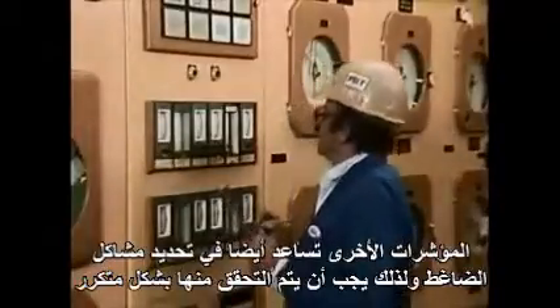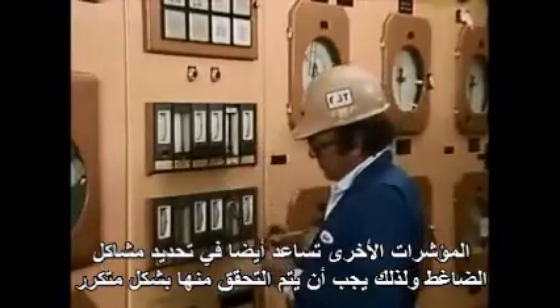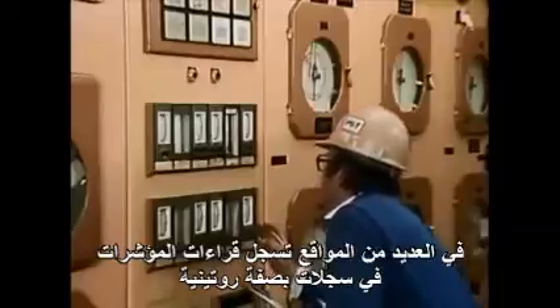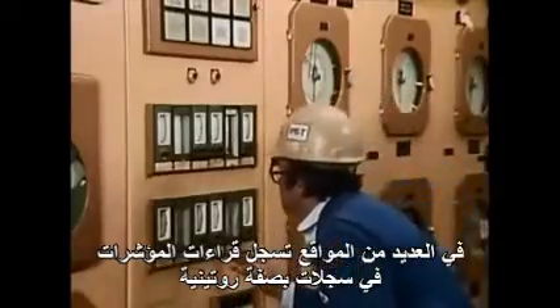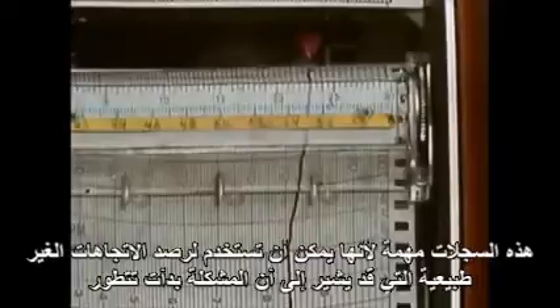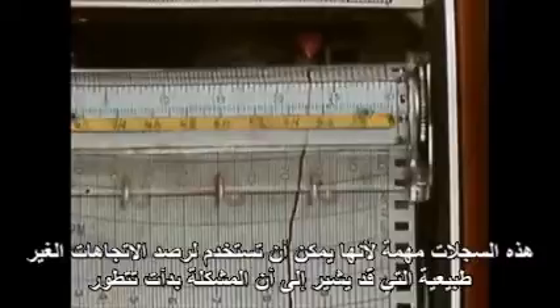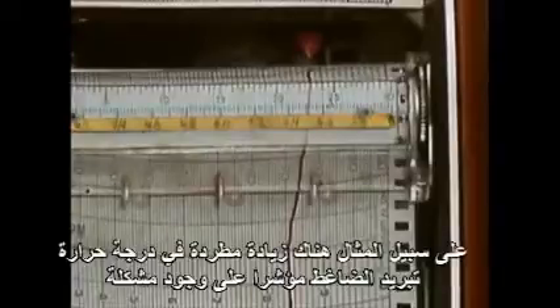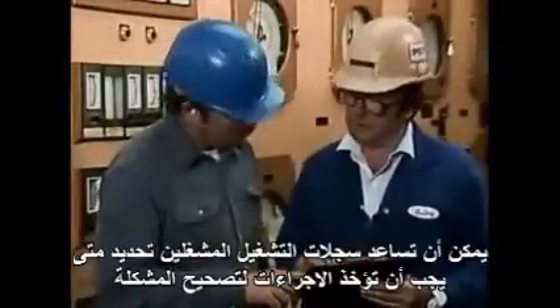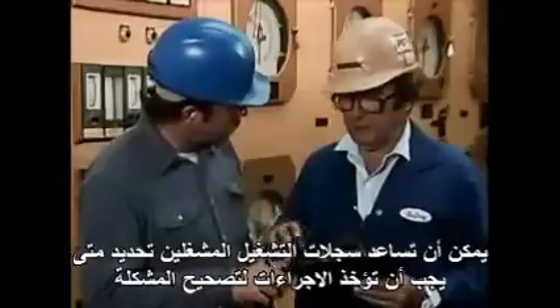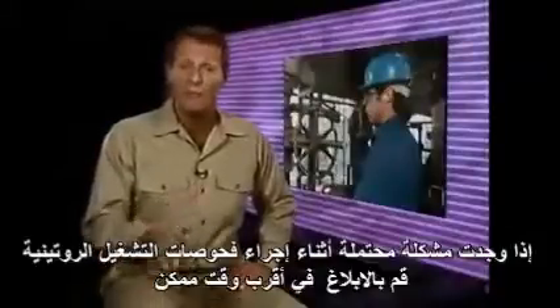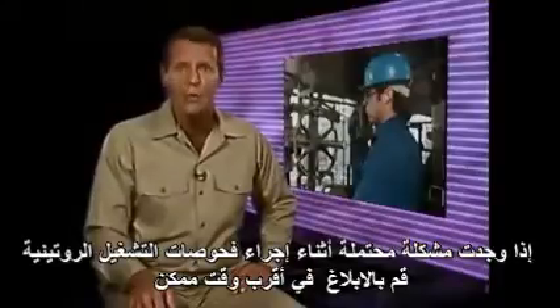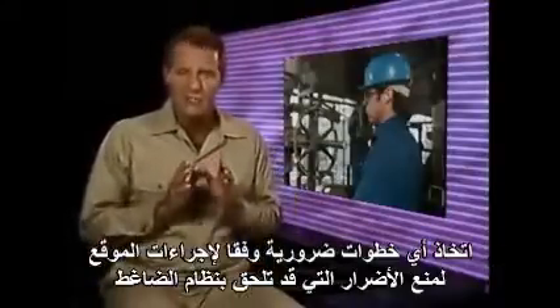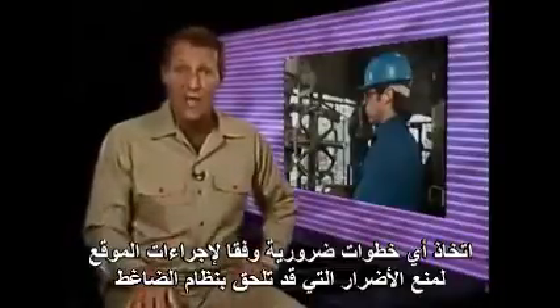Other indicators can also help identify compressor problems, so they should be checked frequently. In many facilities, indicator readings are recorded on a log sheet on a routine basis. These records are important because they can be used to spot abnormal trends, which can indicate that a problem is starting to develop. For example, a steady increase in the compressor's cooling system temperature may be an indication of a problem. Operating records can help operators determine when actions need to be taken to correct problems. If you find a potential problem while you're making routine operating checks, report it as soon as possible. Take any necessary steps according to plant procedures to prevent damage to the compressor system.